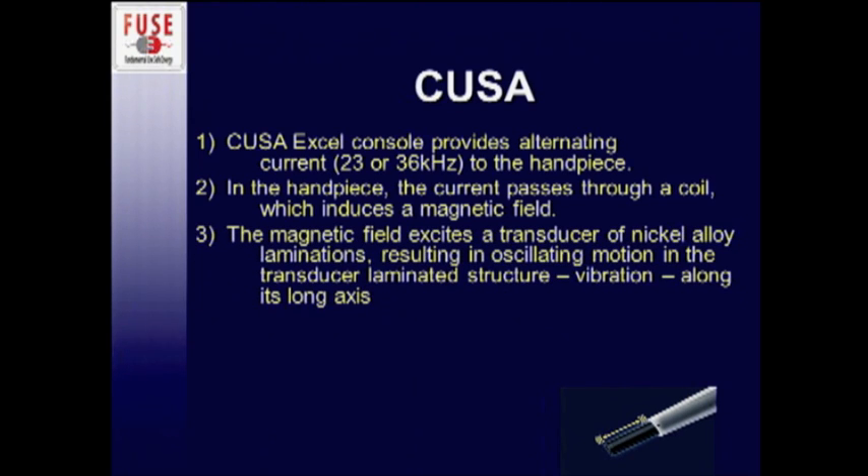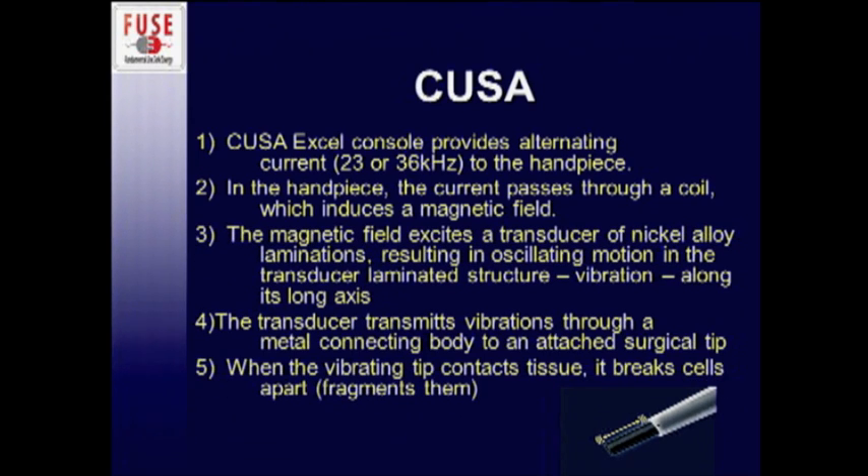The CUSA Excel console provides an alternating current of either 23 or 36 kilohertz to the handpiece. In the handpiece itself, the current passes through a coil which induces a magnetic field. The magnetic field excites a transducer of nickel alloy laminations, resulting in oscillating motion — vibration along its long axis. The arrow in the picture shows the direction of that vibration. The transducer then transmits vibrations through a metal connecting body to an attached surgical tip.